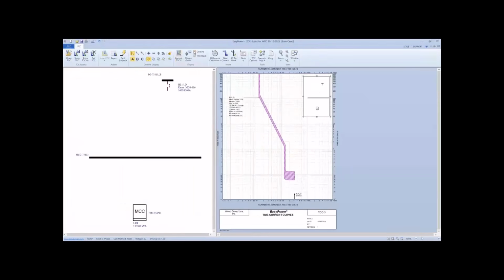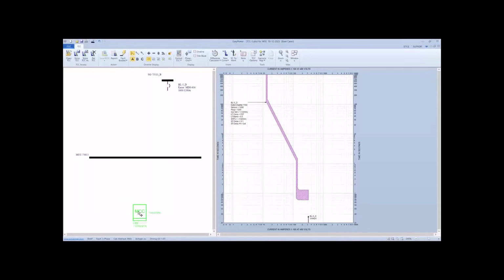I hide this to make the TCC bigger. We check the MCC, the arc flash of this. It's not bad. So in order to look at the arcing current, right click on the breaker TCC, and we have the insert arcing current tick mark, and it's here. For that reason, the arc flash is good, because the breaker is seeing this current, so it operates very quickly if there is an arc flash.